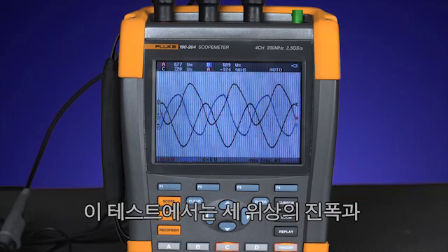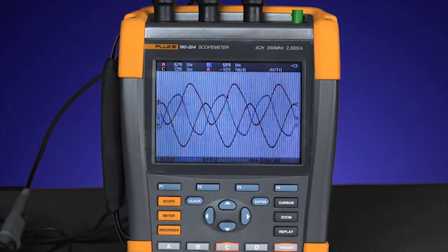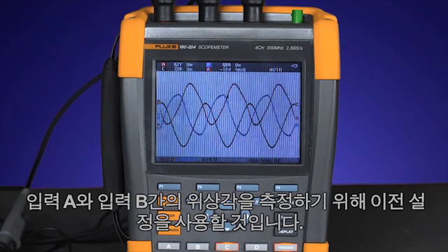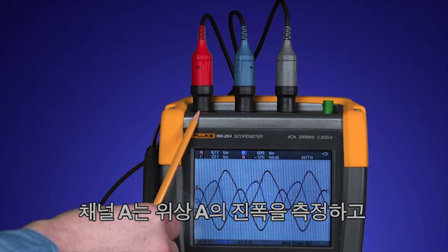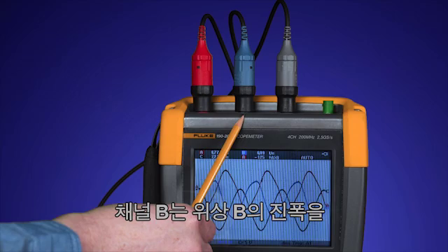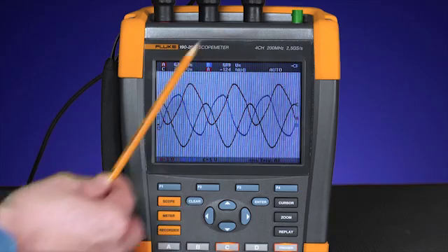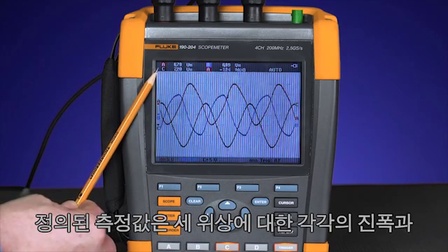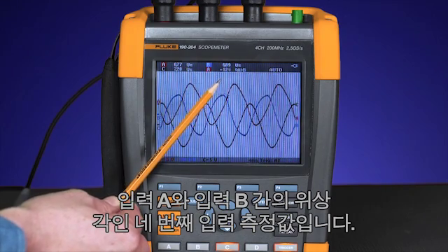For this test, we'll be using the previous setup to measure the amplitude of the three phases as well as the phase angle between input A and B. We have our inputs set up with channel A measuring the amplitude of phase A, channel B measuring phase B, and channel C measuring phase C. Our defined measurements are the amplitude on each of the three phases and the fourth input reading the phase angle between input A and B.